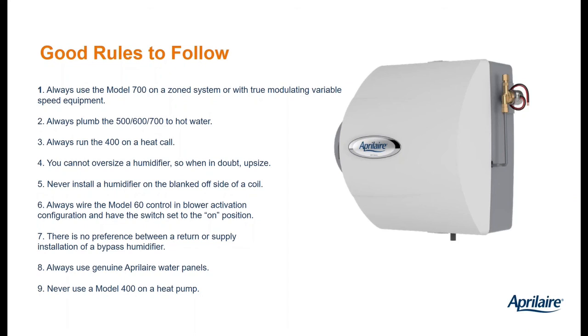And this last one here, never use a model 400 on a heat pump. I think that's grossly overstated. Lots of people put 400s on heat pumps, but you have to remember water, airflow, heat. Heat pumps are going to have a lower plenum temperature. They're going to output about 90 degrees. So that's not as hot as a fossil fuel furnace, so you have fewer BTUs available on the air temperature side.